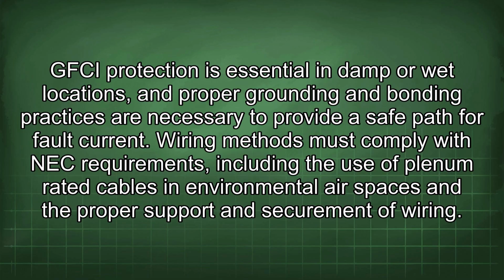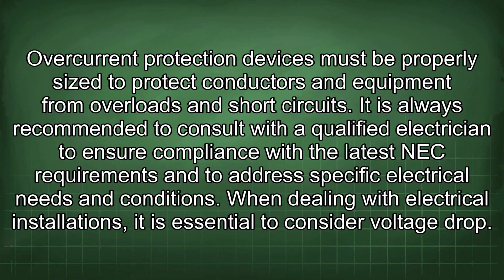Wiring methods must comply with NEC requirements, including the use of plenum-rated cables in environmental airspaces and the proper support and securement of wiring. Overcurrent protection devices must be properly sized to protect conductors and equipment from overloads and short circuits. It is always recommended to consult with a qualified electrician to ensure compliance with the latest NEC requirements and to address specific electrical needs and conditions.